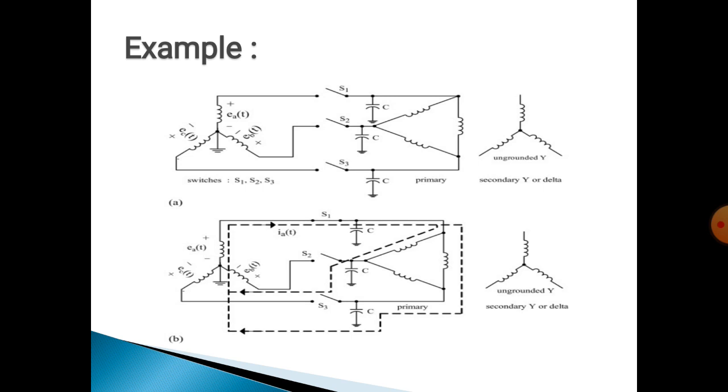Now consider one pole switch is closed, then the transformer is not energized, but there is a path for the flow of current through two of the remaining phase windings and the cable capacitance of those two phases. This current flowing in the specified path can produce resonance and impress excessive voltage across the transformer and the cables on the unenergized phases.